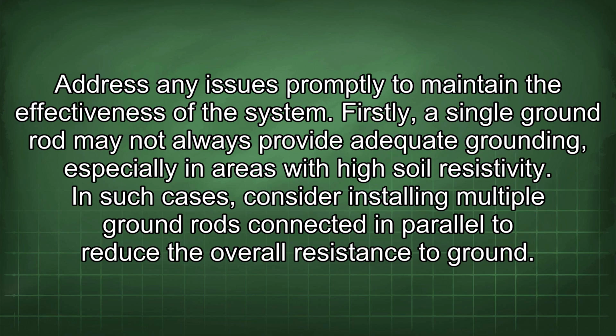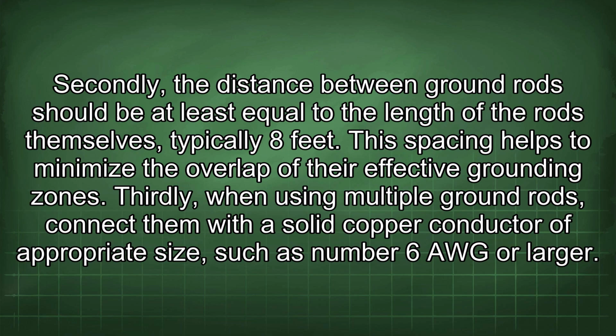Firstly, a single ground rod may not always provide adequate grounding, especially in areas with high soil resistivity. In such cases, consider installing multiple ground rods connected in parallel to reduce the overall resistance to ground. Secondly, the distance between ground rods should be at least equal to the length of the rods themselves, typically 8 feet.